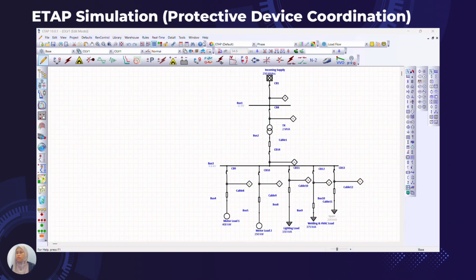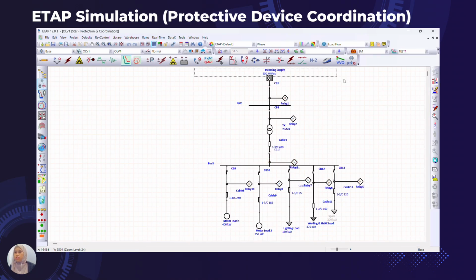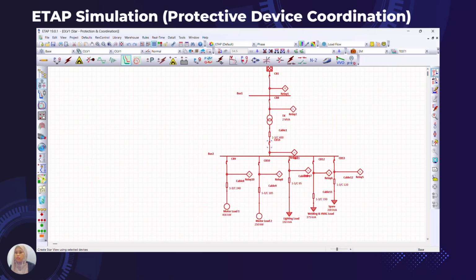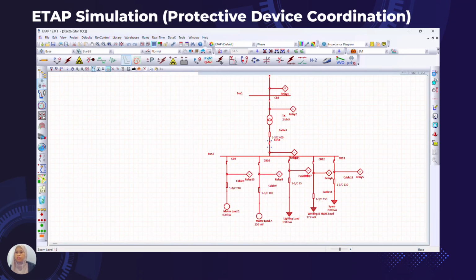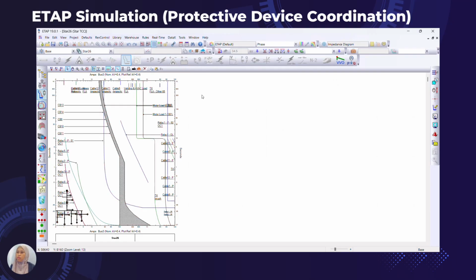For protective device coordination, before we run the simulation, we have to add 3 components at each bus bar. First, we have to add circuit breaker, current transformer, and also the relay. Then we go to the protection and coordination star. Then we have to select the entire SLD. Then click create star view. Then this is the time current characteristic curve for protective device. That's all from me. I will pass to MAHFUZAH, SYAIFUDDIN, and NORAMIRAH to explain the result of the simulation.